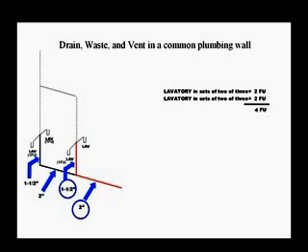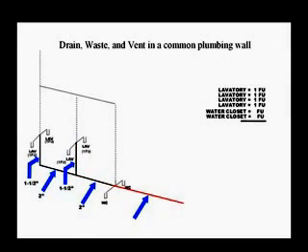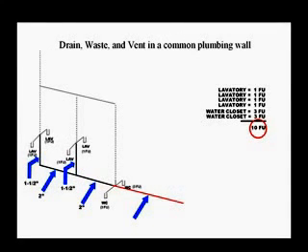If we add two water closets, refer to table 7-3, locate water closet 1.6 gallon per flush gravity tank, and see they are rated at 3 fixture units each. Adding these additional fixture units to the existing fixture units, we have a total of 10 fixture units needing to be drained through this section of pipe.